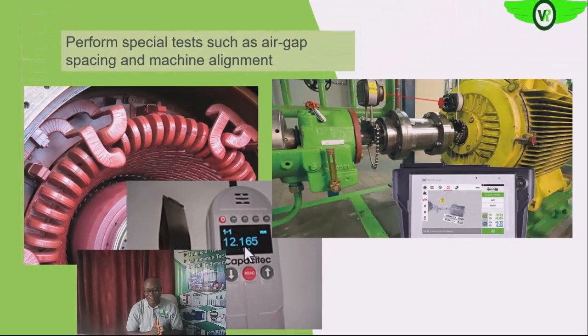Another test that we can do under the physical and mechanical tests is the alignment test, to be sure that the equipment is aligned. As you can see, we can align the driven equipment to the driver, which is the electric motor, because if they are not properly aligned, that will exert excessive stress on the bearings, and that can eventually lead to bearing failure. Bearing failure will eventually lead to failure of the machine itself, and cause other problems like the rotor rubbing, and once the rotor is rubbing, it can eventually result in burnout.